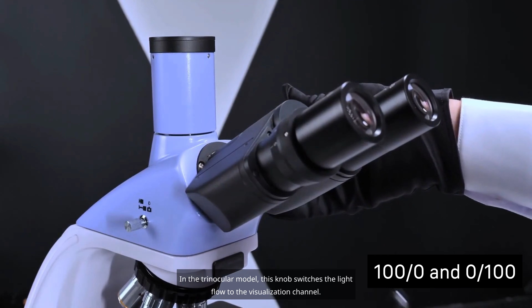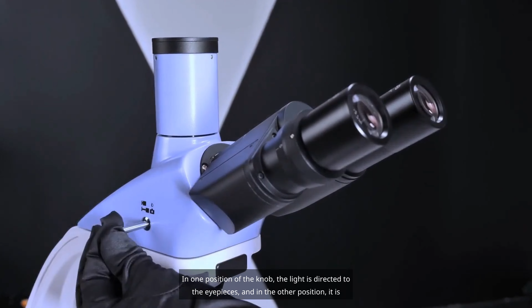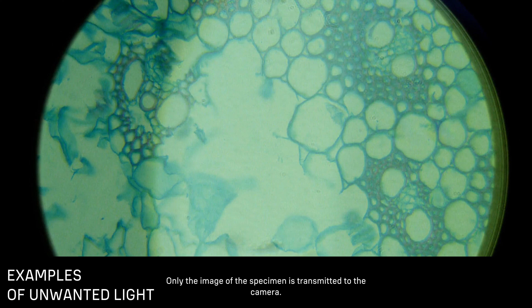In the trinocular model, this knob switches the light flow to the visualization channel. In one position of the knob, the light is directed to the eyepieces, and in the other position, it is directed to the third channel. This switching method ensures that the brightness of the light source is sufficient for use with any objective, not only for the bright field method, but also for the dark field and phase contrast methods. The second interesting property of such a light flux distribution is the absence of parasitic illumination. Only the image of the specimen is transmitted to the camera. Light entering the eyepieces from external sources will not pass into the visualization channel, and reflections from the ceiling light bulb will not ruin your photograph.